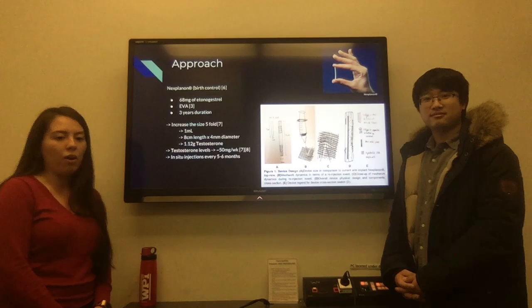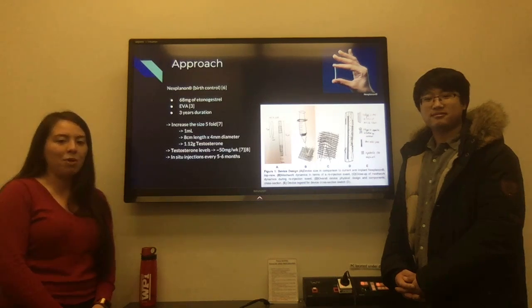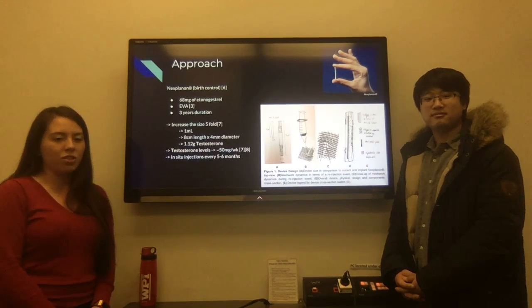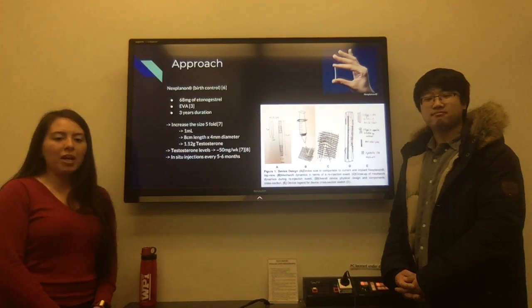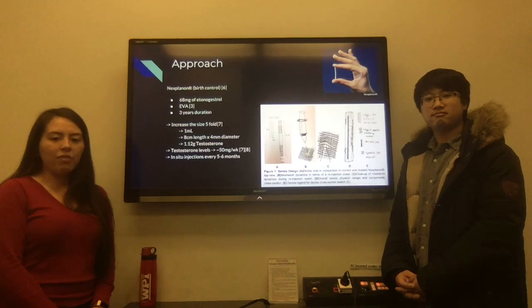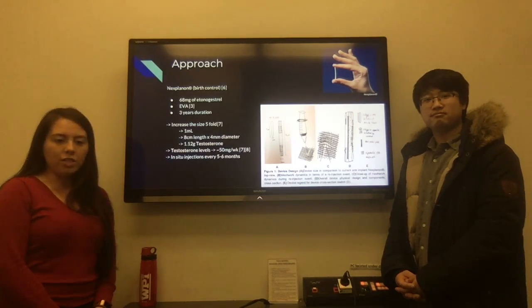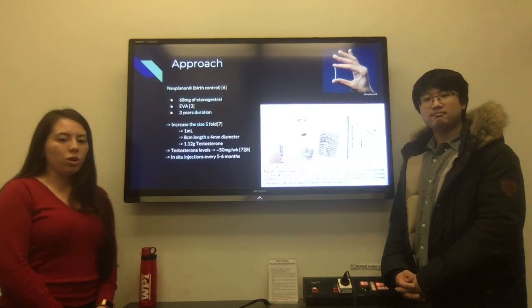Therefore, our product would be able to carry at a maximum 1.12 grams of dry testosterone that would dissolve through the meshwork as fluid comes into contact with it. For a patient who is prescribed a dosage of 50 milligrams per week, this device would last about 6 months. However, due to the metal lining of the device, the patient will have the option to return to the clinic or inject themselves with a higher or lower dose depending on how their hormone levels are.